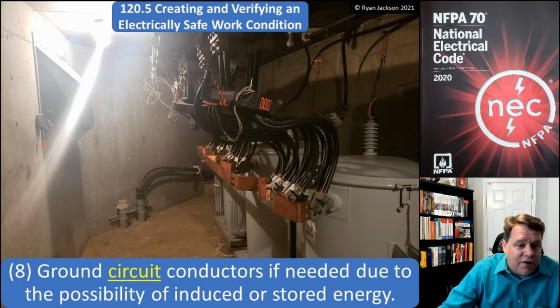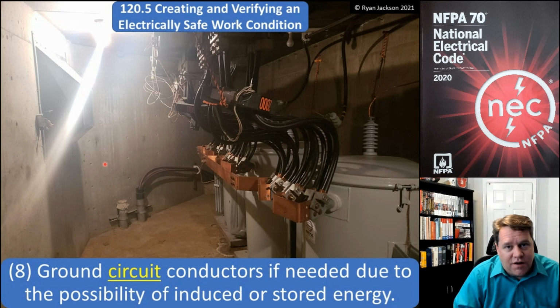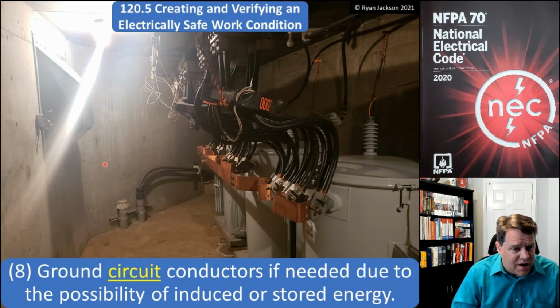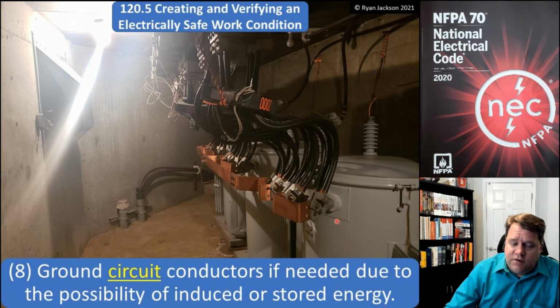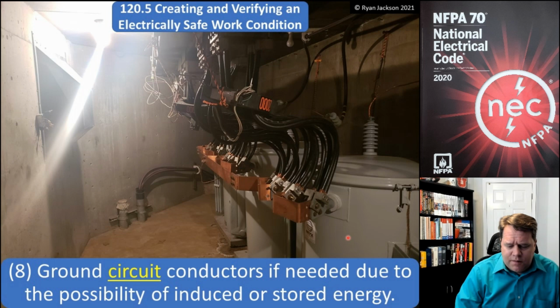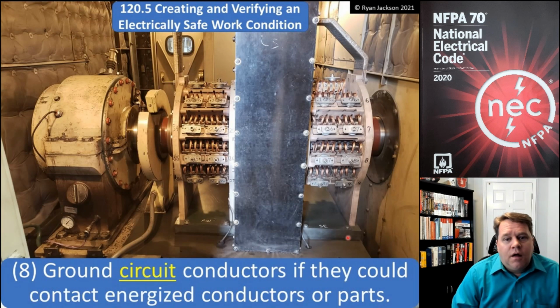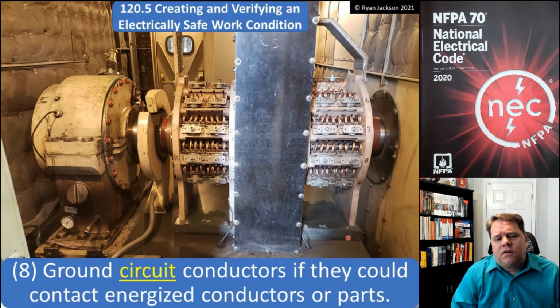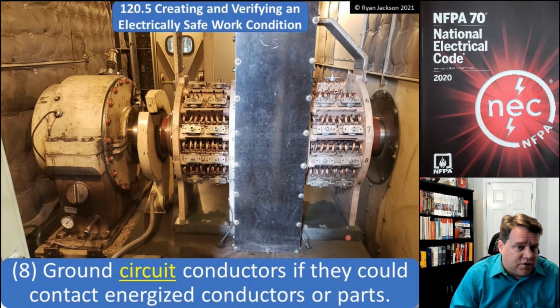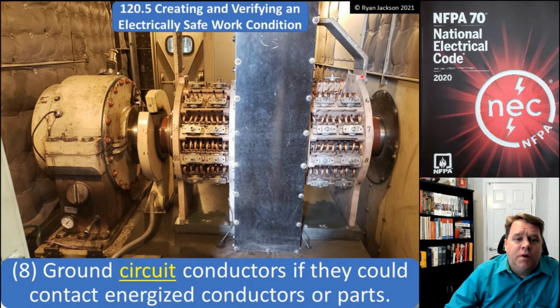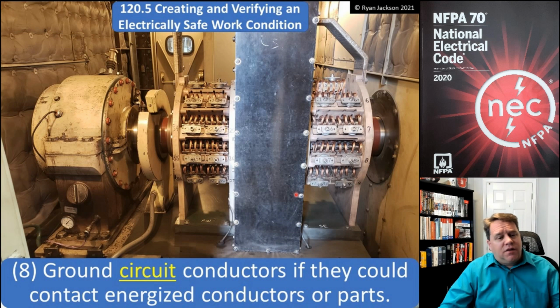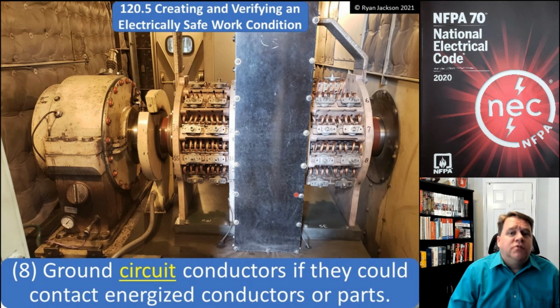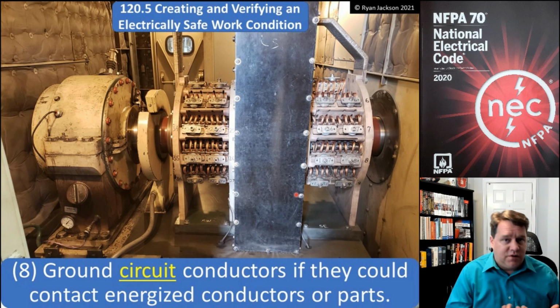So if that is possible, then we need to ground the circuit conductors to prevent any induced voltage from injuring us. So not something that we have to do every time. It does say if needed. And at lower voltages, this becomes a less common occurrence, but it's definitely not something that you need to ignore. The other item is ground the circuit conductors if they could contact energized conductors or parts. If I'm working near open energized parts like this exciter for a generator, I might need to ground the circuit parts that I'm working on so that if there's accidental contact, it doesn't energize them.